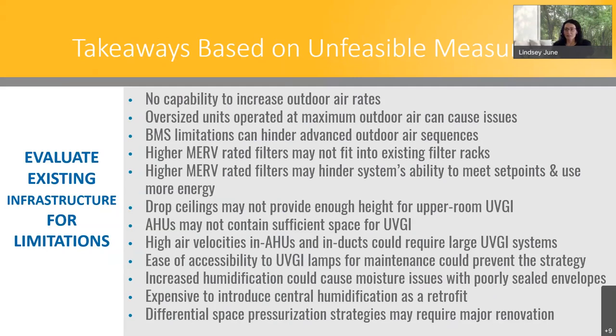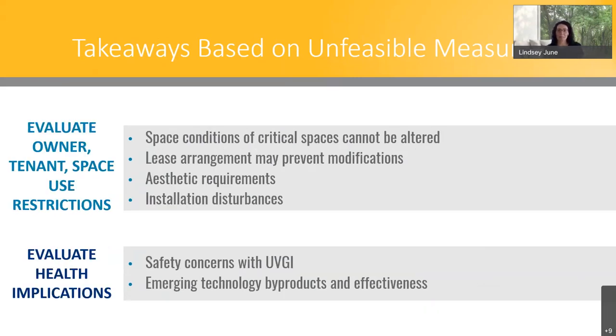All right, next slide. Another consideration is owner, tenant, and space use restrictions. Some HVAC units serve critical spaces, such as healthcare and museum settings, and can't be altered in any way that would impact those space conditions. Lease arrangements may also prevent modified settings and operation and system implementation, depending on who owns or operates or has control of the unit. And then aesthetic requirements are a real consideration. So for example, upper room UVGI is most beneficial in large assembly spaces, but if these spaces are within tenant areas, it may require tenant buy-in. And then there's also the installation disturbances that need to be factored in.